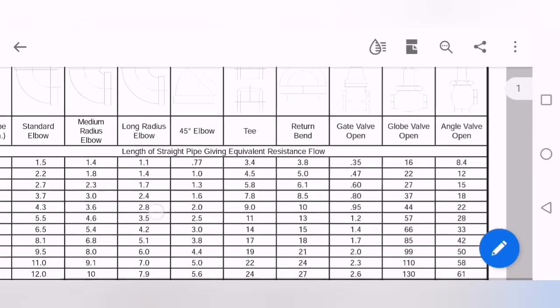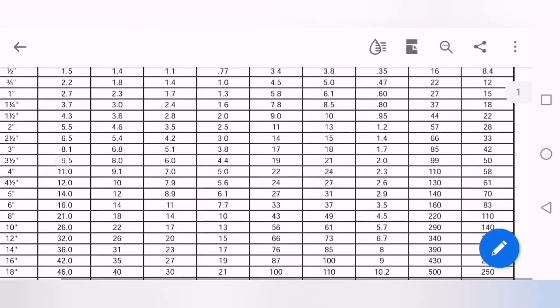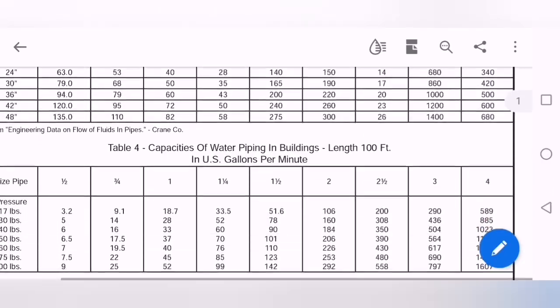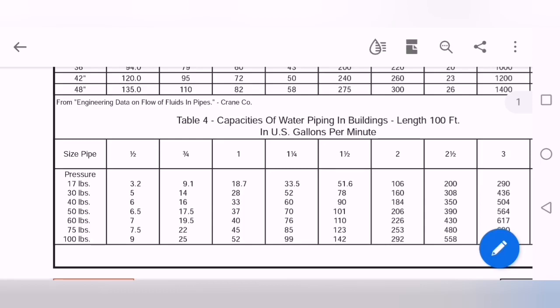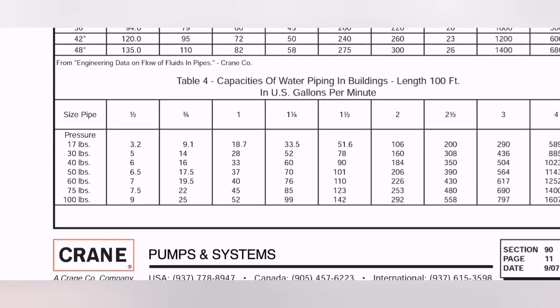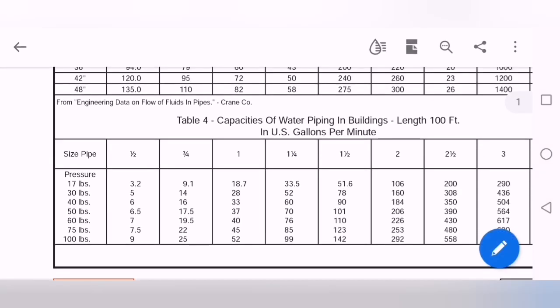Same for the gate valves, globe valves, and angle valves. Now the main concern is pipe length. If you have 100 feet of length, I have below 100 feet, 95 something, and I need 60 pounds of pressure in my pipe. So here you can see one and one-quarter and 60 pounds, there is 76 gallons per minute.